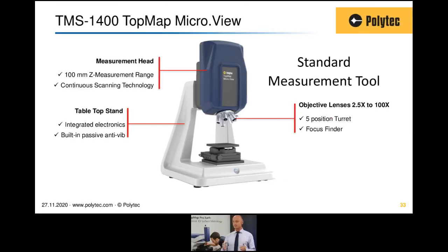The turret is 5 positions. We have this additional hardware option. So instruments of this type normally come with some kind of pre-scan autofocus to allow you to find the surface. We have additional software to offer you an enhanced focusing capability. We have built into the system a focus tracker so you can follow your surface. So this really complements automation capabilities.